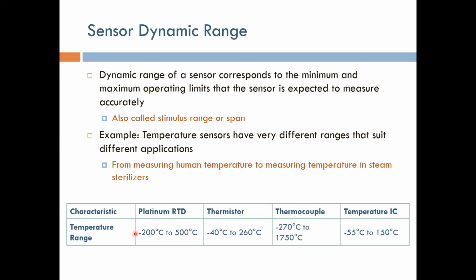In this case, probably RTD would be very suitable, thermocouple would be suitable, but thermistors and temperature ICs are not, because they cannot withstand 400 degrees, for example, in either case. If you're trying to melt iron, using really high temperature furnaces to melt metals and form them into particular alloys or similar things, you need a temperature sensor to make sure you are at the right temperature.